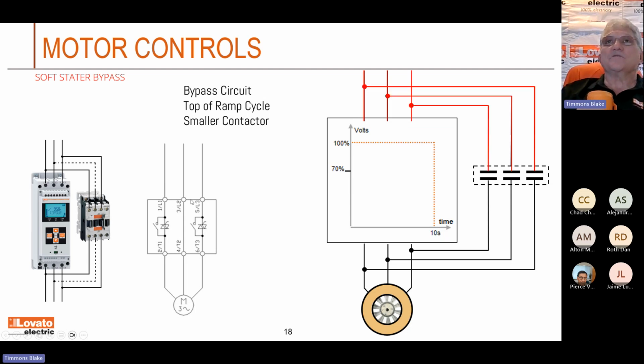So what happens is you'll supply your voltage, and almost all these soft starters now have a little bypass contactor built in them. Okay. Well, used to we'd ask, does that have a bypass in it? Well, why do you want a bypass? Because after you've done all the ramping, this thing doesn't need to sit here and run through the SCRs. You can run it through a little bypass contactor, and it can be a little smaller because you don't have that inrush current.